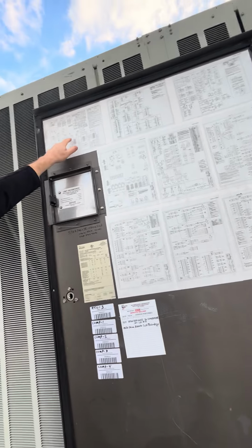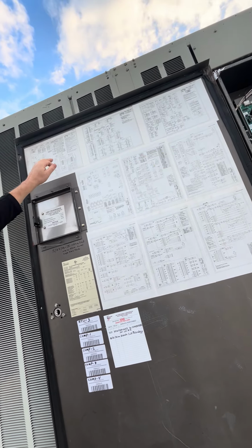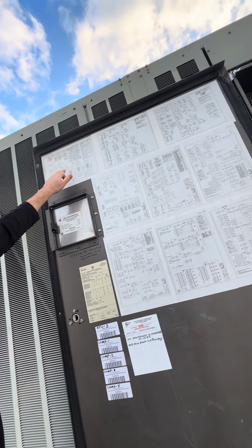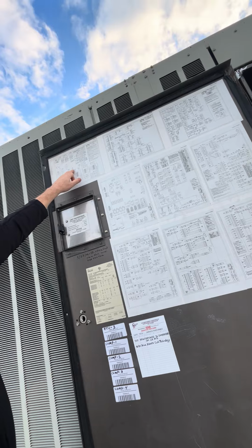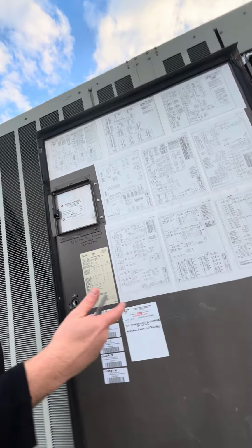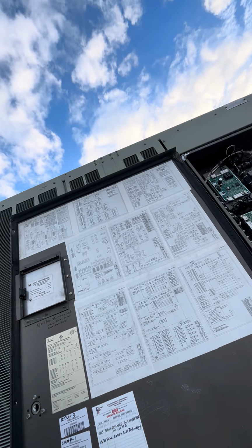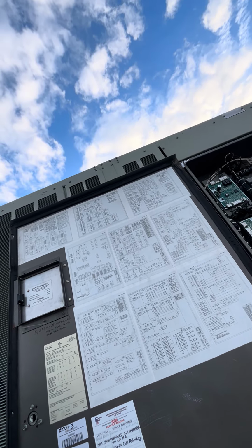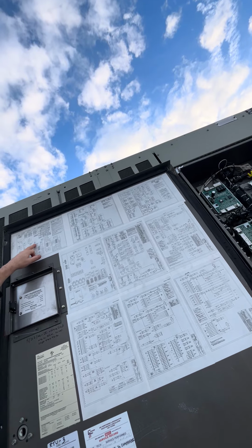So what we do is in the user interface, we will set that to 100%. When you give this a contact closure, the unit interprets that as it locks out 100% of the cooling. Doesn't allow it to run. So that's kind of your cooling enable, kind of like a cooling enable disable.